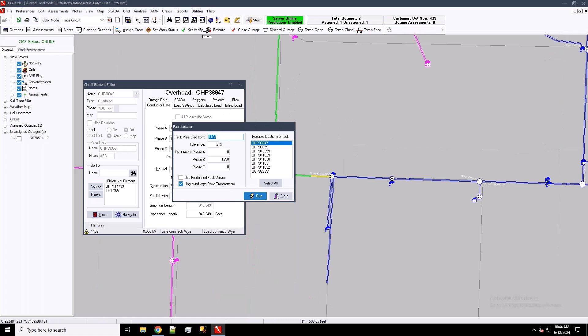I'm currently using a model trace, and that's helpful when I'm looking at these results because the element that I've got selected is highlighted in yellow. Green is upline, going back towards my source. Everything blue is downline. So as I look through these elements, I'll see that fault tracing highlighting, and it certainly looks like we've got a little cluster of elements right in this area where that line splits and heads east and west. That might be great information for me to send my crew. Why don't you start looking for that fault in this particular area?